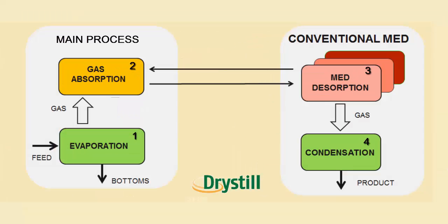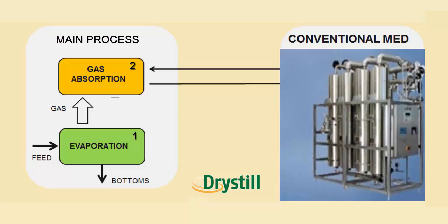The four-step process may be pictured as two independent subsystems, which communicate only through the absorption fluid circuit. Steps three and four serve the ancillary function of absorption fluid reconcentration. There is no new technology here. It is a very ordinary multiple effect evaporator running a clean, well-behaved fluid.